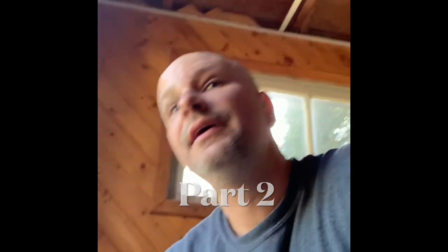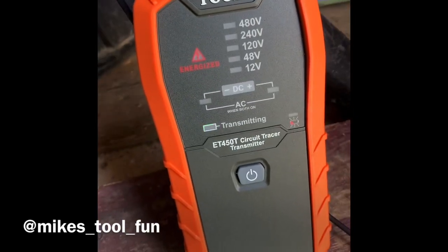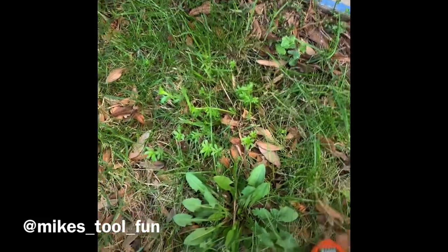So that first video was with the transmitter and power energized to the pump. Now I'm going to try this tool with the circuit de-energized and see what happens. I have the transmitter hooked up — it's de-energized but it is hooked up, and I have my ground hooked up. I'm going to turn this on and crank the signal right up.